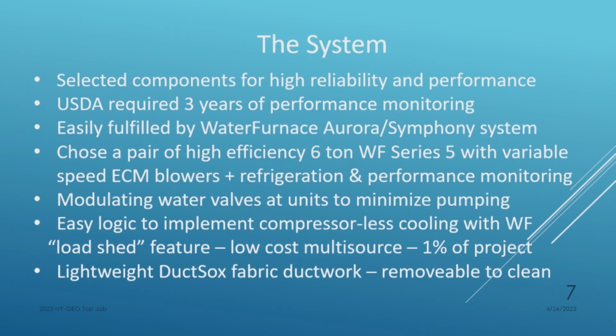And for ductwork, we didn't want a lot of heavy metal ductwork that, first of all, could rust. If it's horizontal, it collects a lot of condensation. These get really humid. So we went with this product called DuctSox. If you've never seen it, it's a fabric. It gets hung on a track, and it just hangs like this until the air blows, and it blows out, and then it's uniform along the whole length. So we got really good distribution of air. Temperature control was a whole lot better. And the duct socks, you can take down and clean. So it's kind of a nice thing. And it's kind of translucent, so you can see if dirt and mold are growing inside.